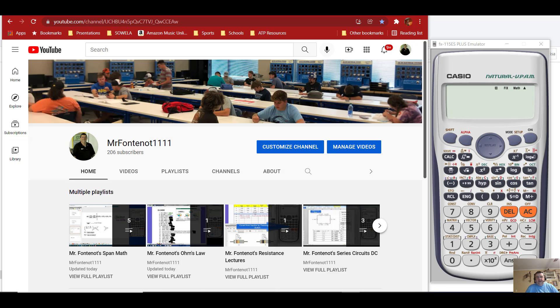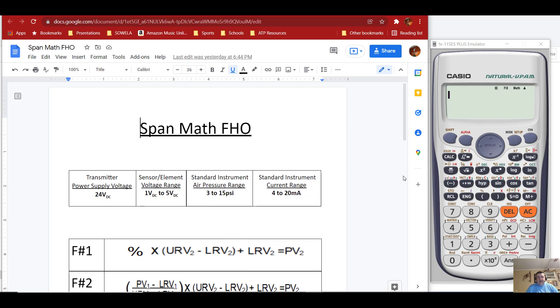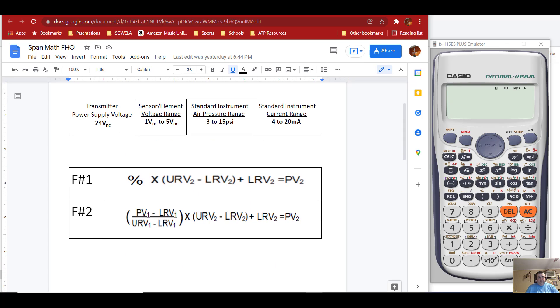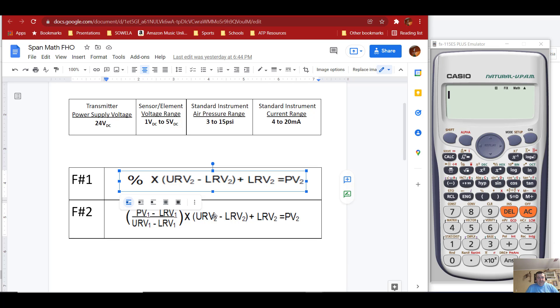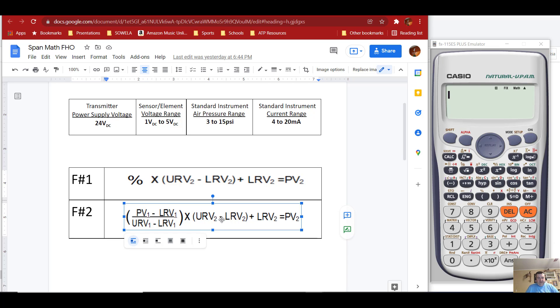The calculator I'm using is the Casio FX-115ES+, first generation. I'm going to be using this information to solve these equations. Transmitter voltage: 24 volts DC, 1 to 5 volts DC range. Standard instrument pressure is 3 to 15 psi. When we're looking for milliamps, we refer to the 4 to 20 milliamp range. If we're given a percentage we'll use formula number one, and if we're looking for a percentage or any other values we'll use formula number two.